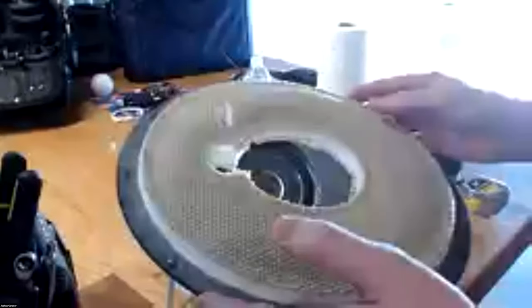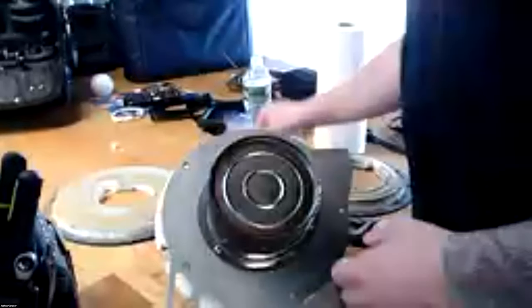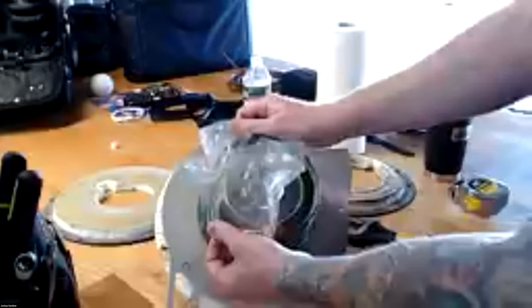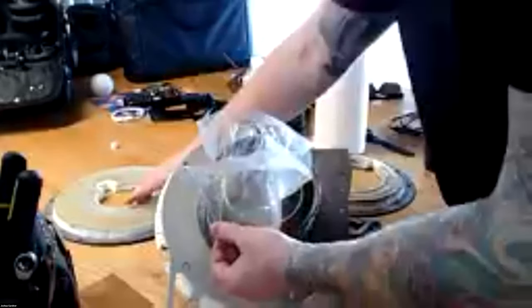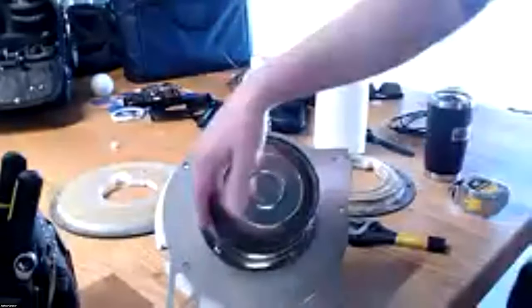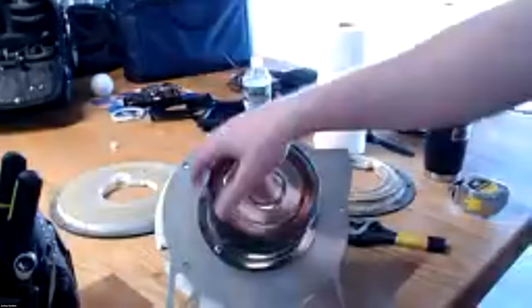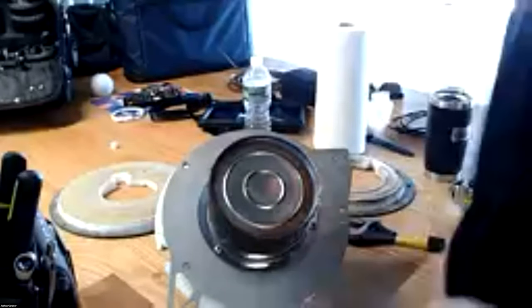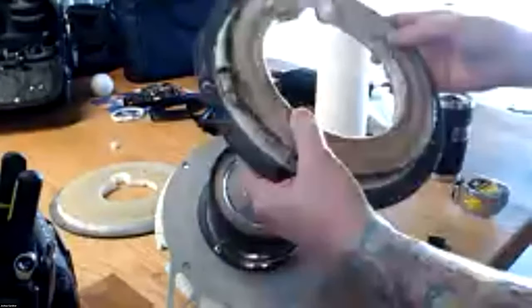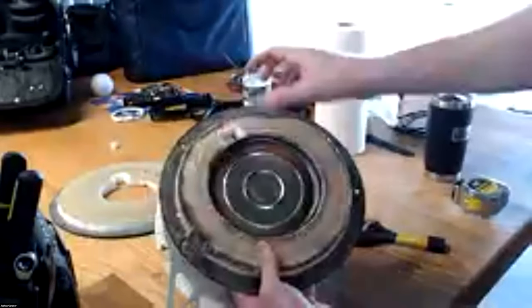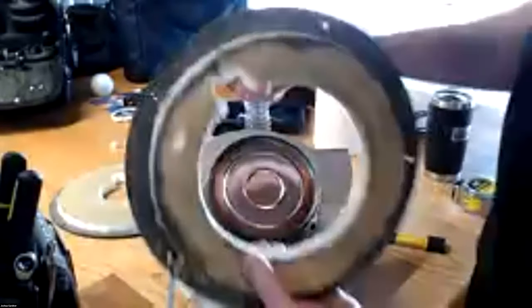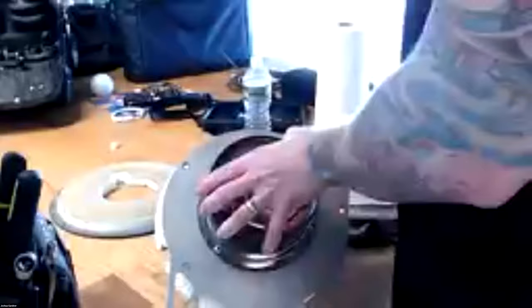This thing comes in a plastic bag. Take that plastic bag, put it over the burner head, and then slide the insulation over that, and then remove the plastic bag. And that will prevent any of this insulation getting caught up in the burner head. Cool. So that's a little trick on the reinstallation. So if you do have to reinstall the same gasket, you pulled it off, just put a plastic bag on there and put it back on. So cool. That's a little something to keep this nice and clean.